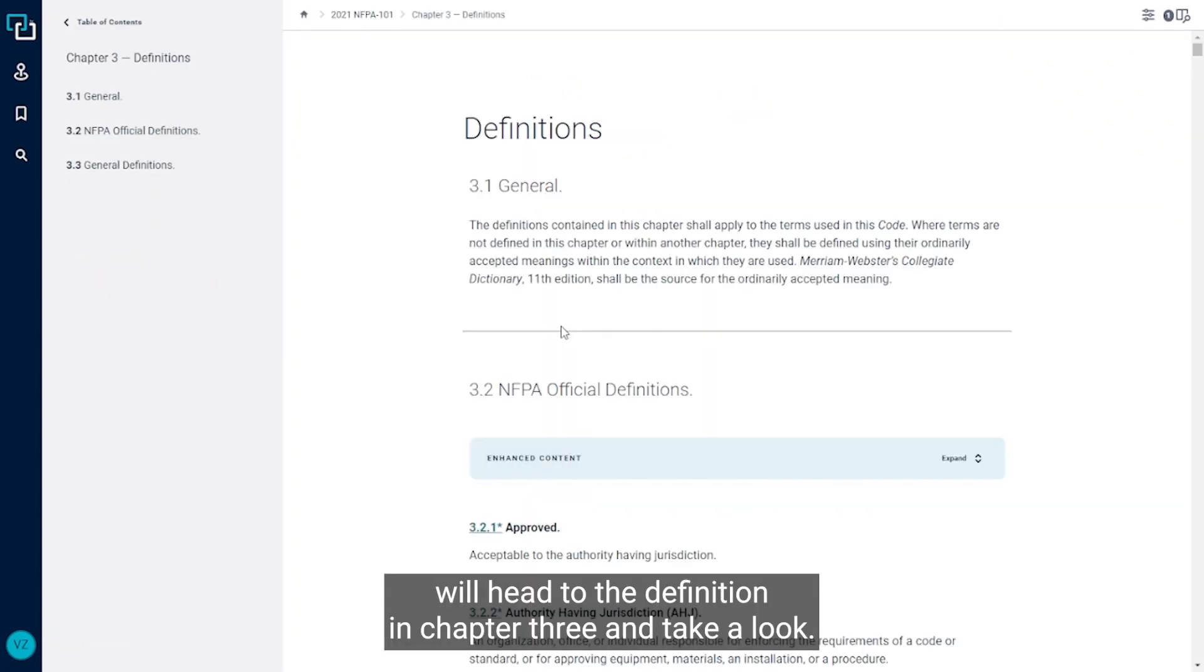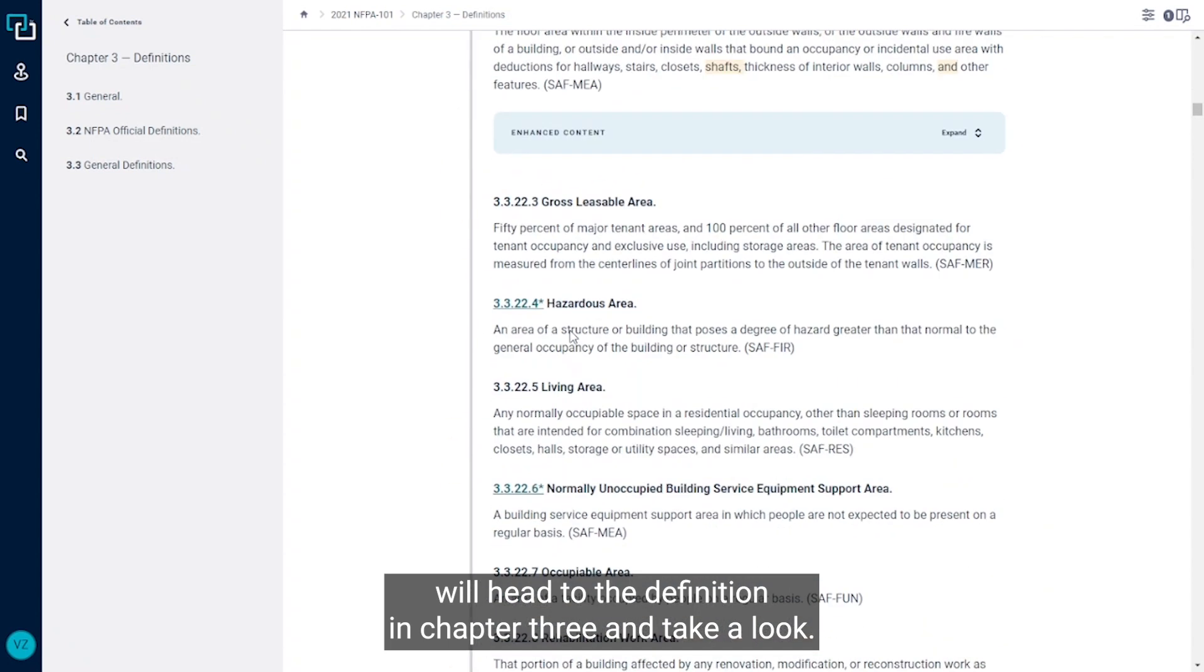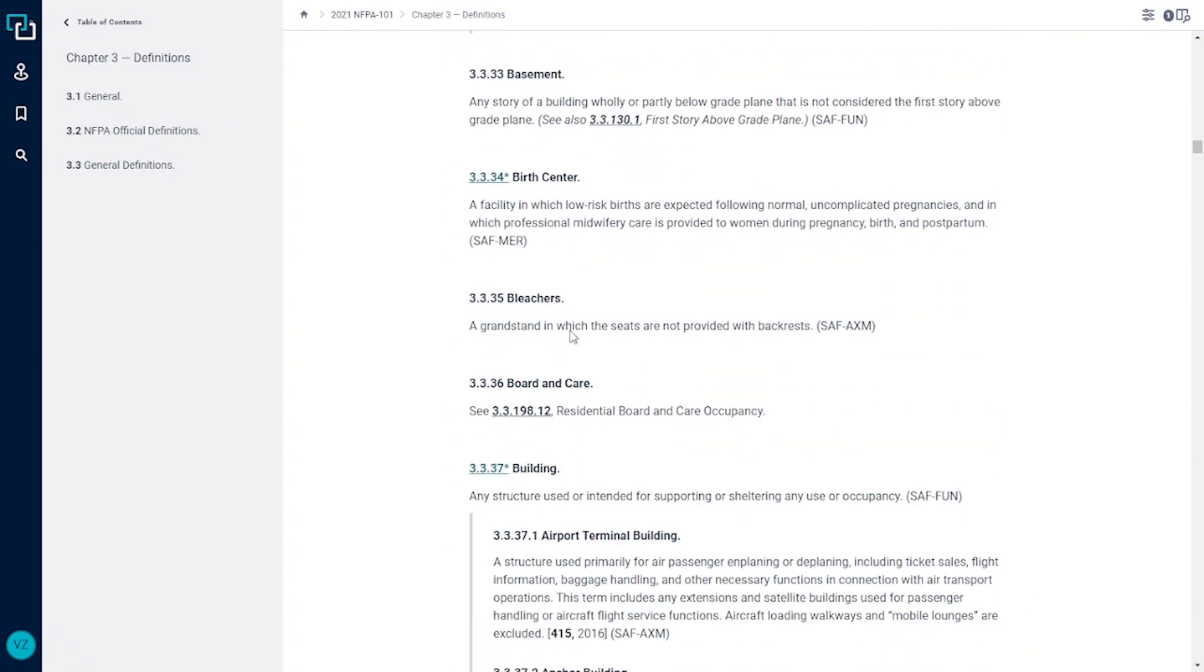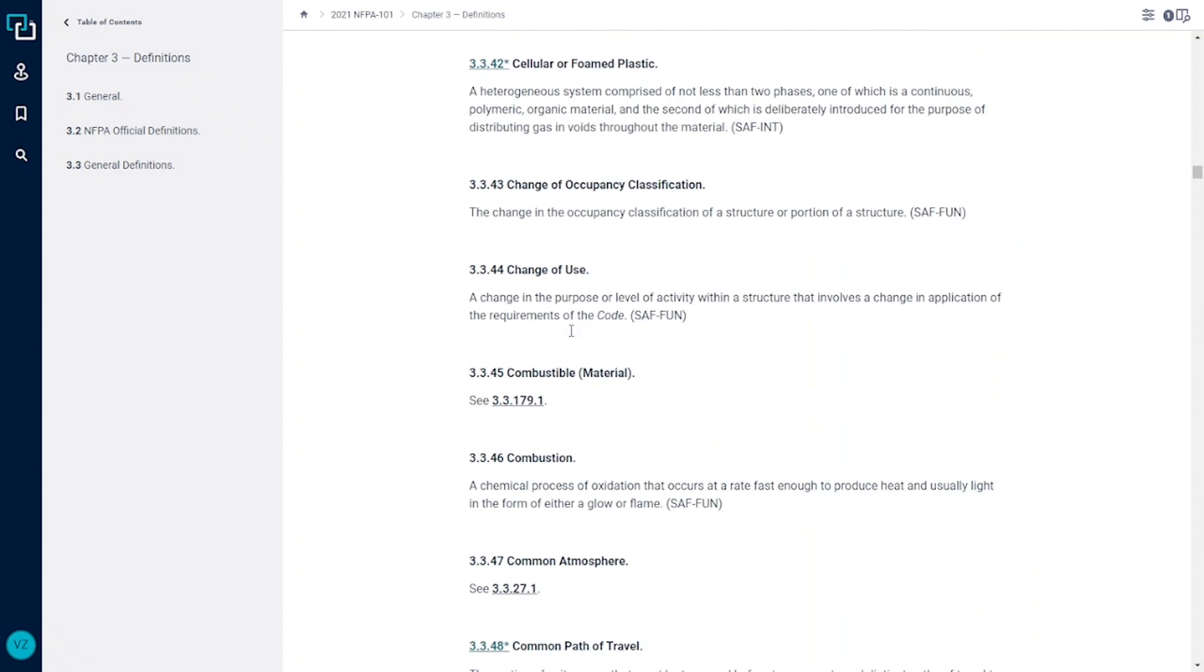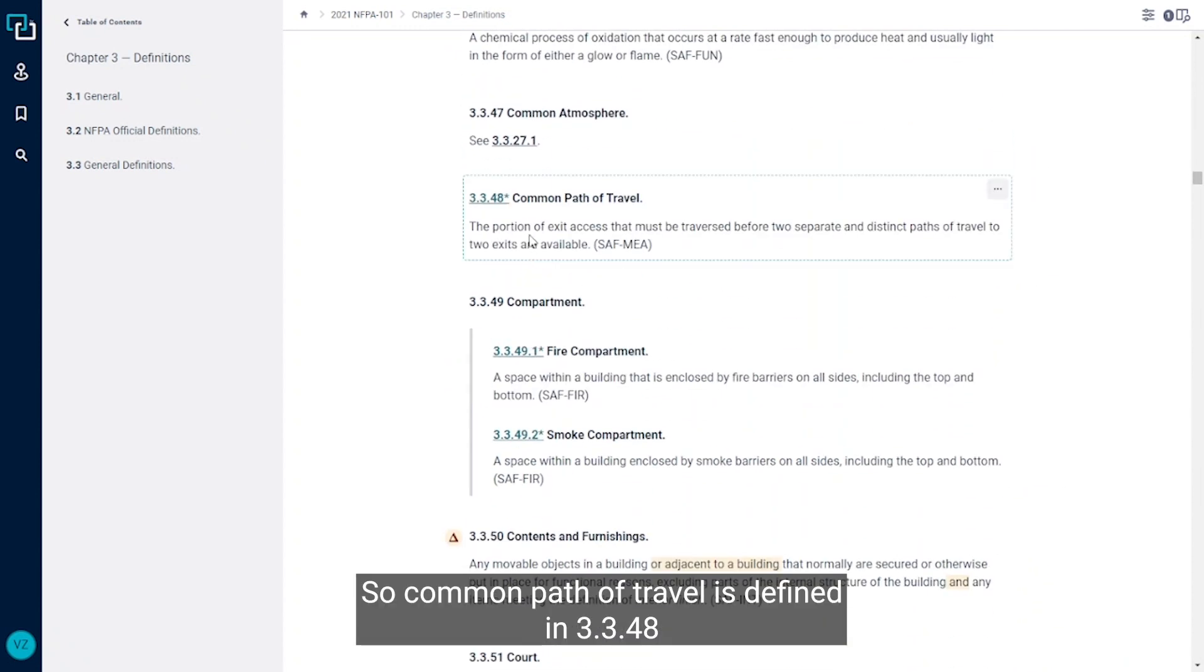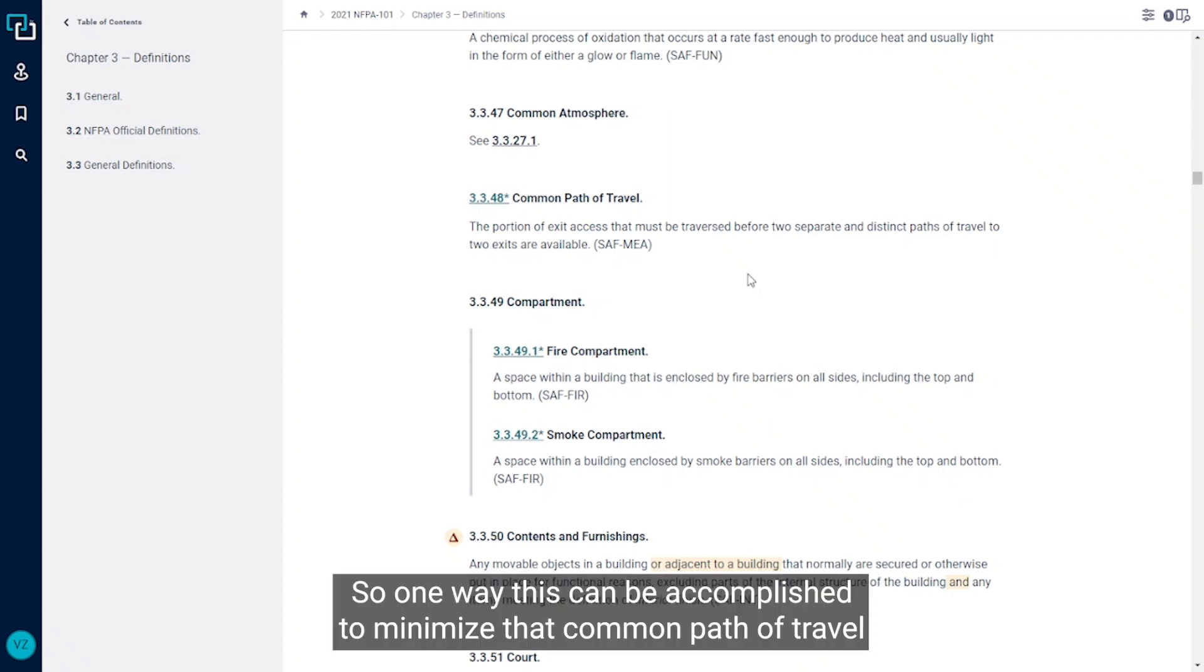If you're not familiar with what common path of travel is, we'll head to the definition in chapter 3 and take a look. Common path of travel is defined in 3.3.48 as the portion of the exit access that must be traversed before two separate and distinct paths of travel to two exits are available.